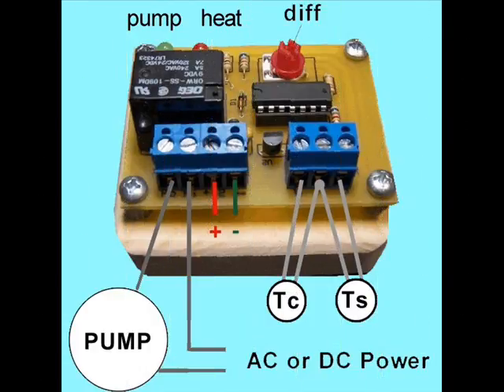The voltages given in this example are only approximate, but if they are accurate, our differential controller would have a range of 3.3 volts minus 2.7 volts or 0.6 volts. This would translate to a differential temperature range of 15 degrees Fahrenheit.